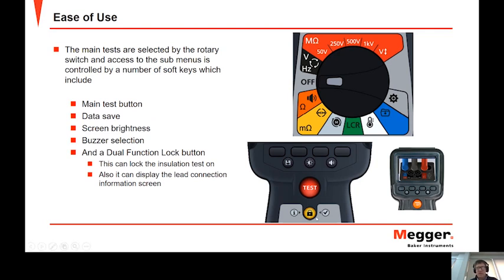And we have this dual lock feature, which allows us to lock the test if we're doing an insulation resistance test, for example, so leave the tester running at that specific voltage. And we can also use this button before we start a test to verify the connections. And when we press it, we will get this image here on the right, which shows us where to connect our test leads to, depending on the test that we're running. And then each test, as you may have noticed, is color-coded. And this is color-coded to match the other Megger test equipment that you may be familiar with. So IR is always red, low ohms winding resistance is always yellow, etc.